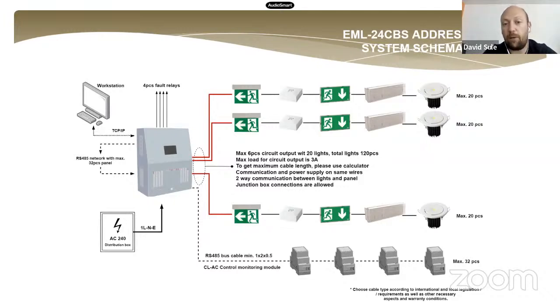We use a 2-core cable, which can be 1.5 or 2.5 in diameter. But because it's a central battery, you should use a 2.5 cable, because the cable length can be longer. I will show what it means for a 1 amp load and for a 3 amp load, how long the cable length can be with 1.5 and 2.5 cable.